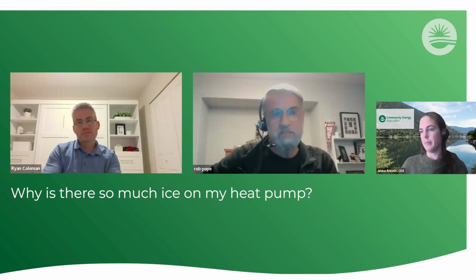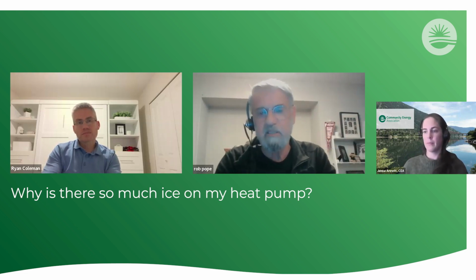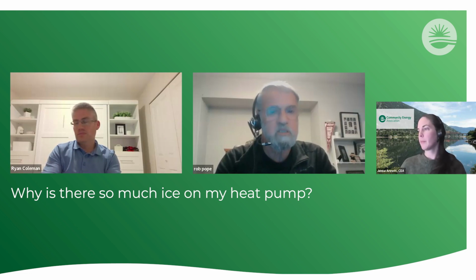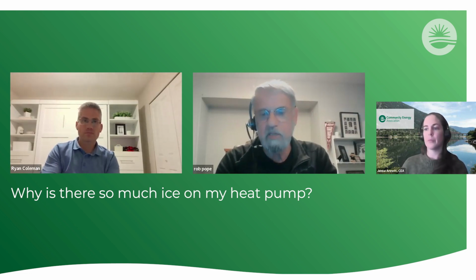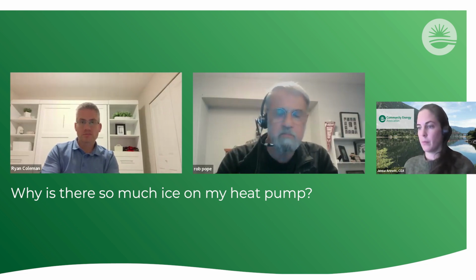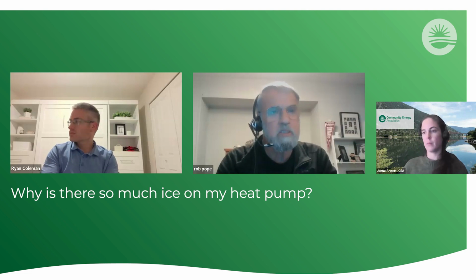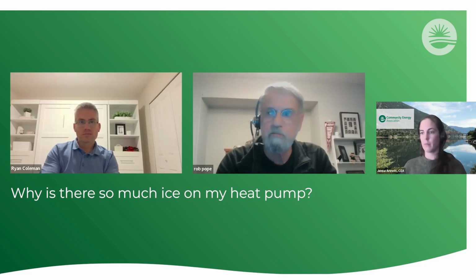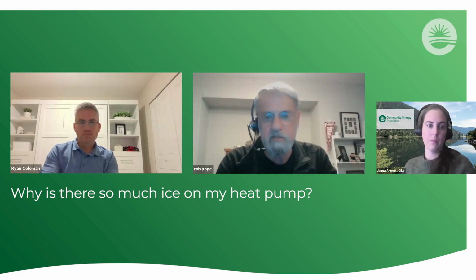Oh, well, that could be a number of things. My first impression is that what we're talking about here is a technical malfunction of some sort. It's not defrosting adequately, and it can be a compounding problem. Once you stop the airflow, it just gets worse. It kind of amplifies itself. So what you have to do is find the source of the problem. It could be a control algorithm. Why isn't it going into defrost as often as it should and as thoroughly as it should? You need a technician on site to answer that question and discover it, because in my mind, it is definitely a control malfunction of some sort going on there.